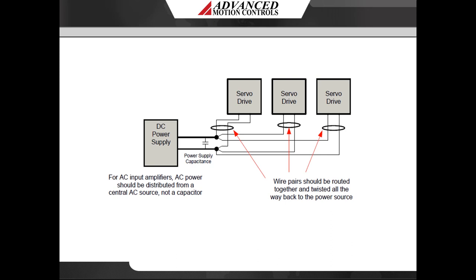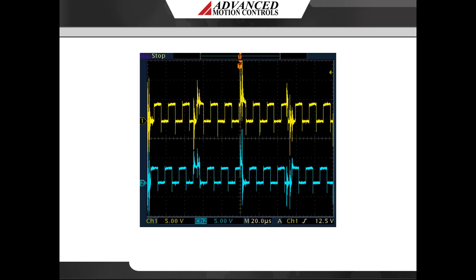PWM switching controls the output by turning the power devices on and off at a high frequency. The fast change in voltage — the DV/DT — appears as capacitively coupled noise spikes on adjacent signal lines. These noise spikes coincide with the PWM switching, where there is a spike every time the power device switches on and every time it switches off. Hence, noise appears at twice the switching frequency. In this oscilloscope capture, noise on the incremental encoder output coincides with twice the switching frequency of a 10 kHz servo drive.